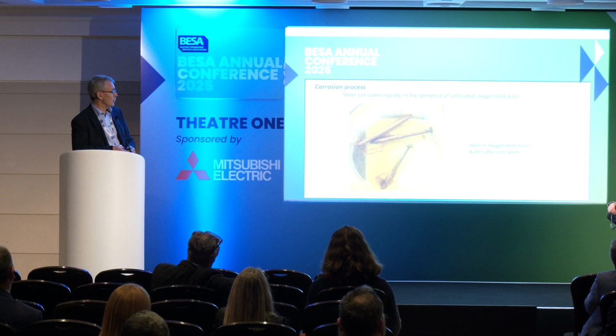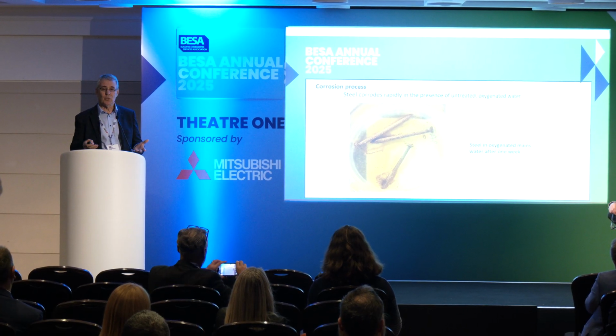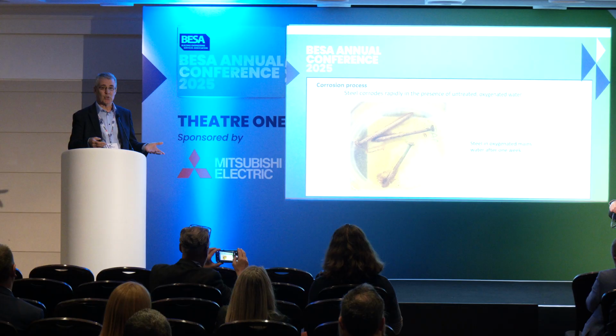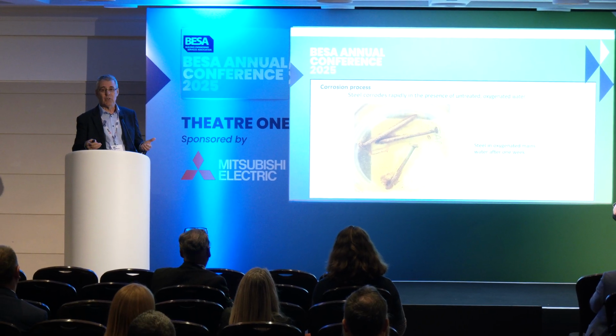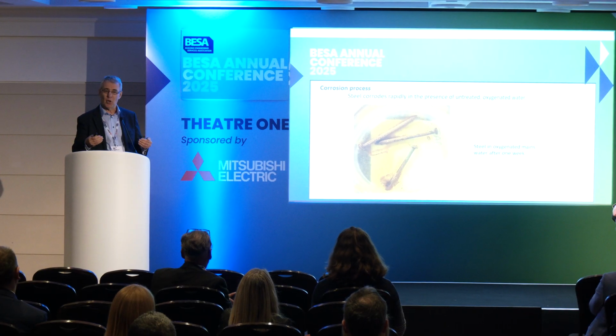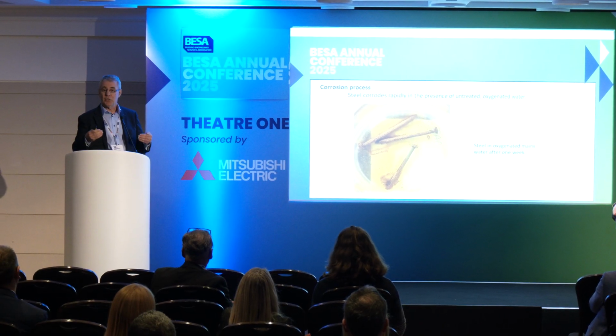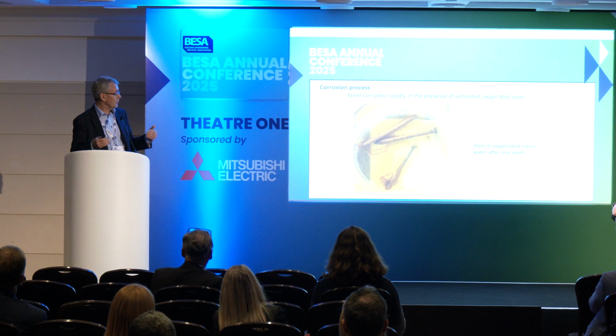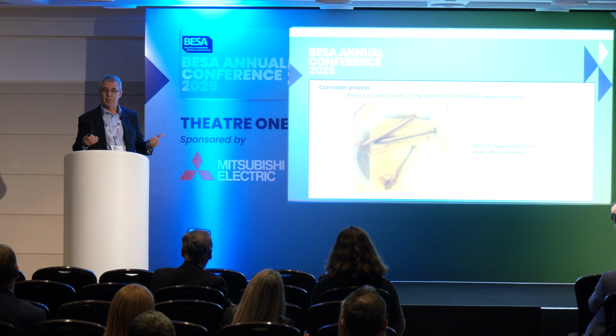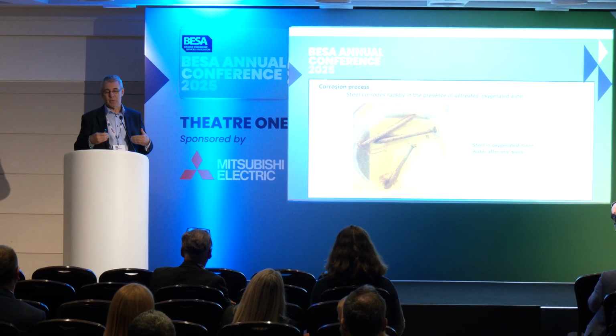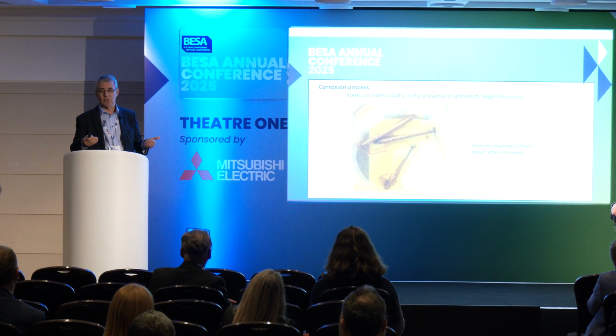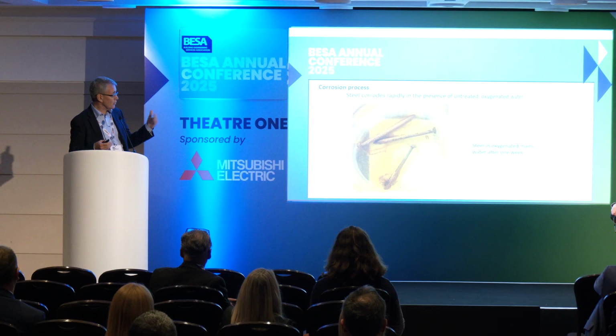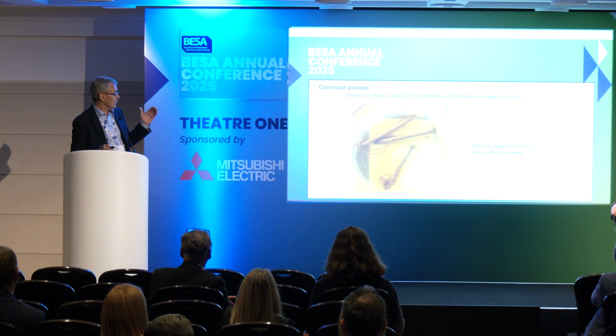If you put steel into oxygenated mains water from anywhere in the UK, it will corrode quite quickly. This is what some people don't grasp, how quick it is. If you go back and look in 24 hours, you start seeing the signs of corrosion. If you leave it a week without any form of treatment, you're then into quite a dirty system. So response is one of the things we emphasize to maintenance contractors: you do have to respond quite quickly. So that's the thing we're trying to prevent.